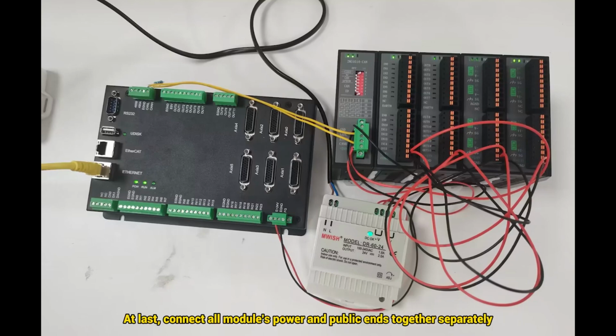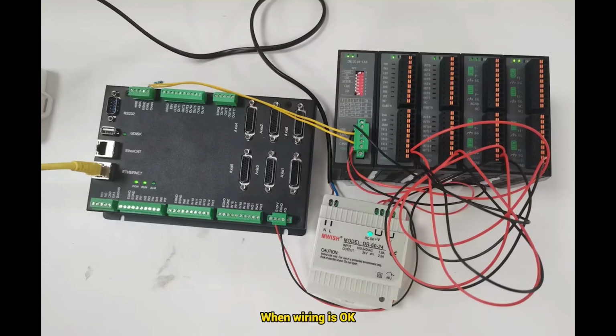In this way, the impedance is matched and the communication can be stable. At last, connect all modules' power and public ends together separately. When the wiring is okay, it can be seen that POW and RUN are on, but ALM and ERR are off, which means the communication is normal. Next, dial Code 1 on, and keep the other 3 off. Now, the combination value is 1.